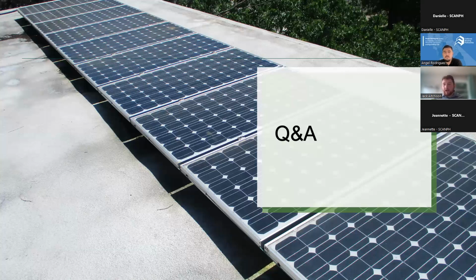Mitsubishi has a CO2 unit out there that has a separate heat exchanger taking on city water. It's outside of their unit because their concern is that if you have hard water in their unit, it's going to result in a faster failure. So they have a water-to-water heat exchanger outside of the unit. You shouldn't have to refill it, but if you do have to refill it because of a leak, you refill the Mitsubishi with distilled water. That is a closed loop heating the city water, sort of like a sacrificial heat exchanger.